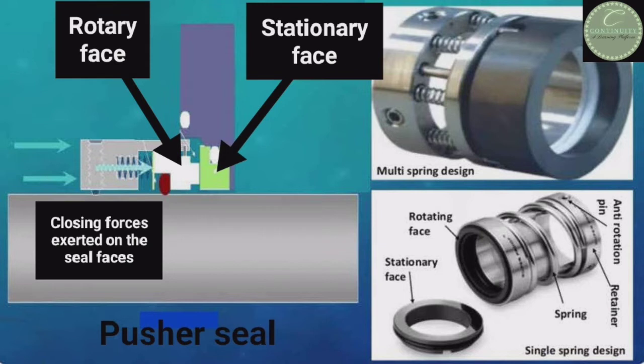This type of seal is used for low temperature and light liquid services such as ethylene, propane, methane, and butane. Looking at this figure, these are pusher seals. The main identification of a pusher seal is that it has a spring — if a seal has a spring or multiple springs, it is a pusher seal.